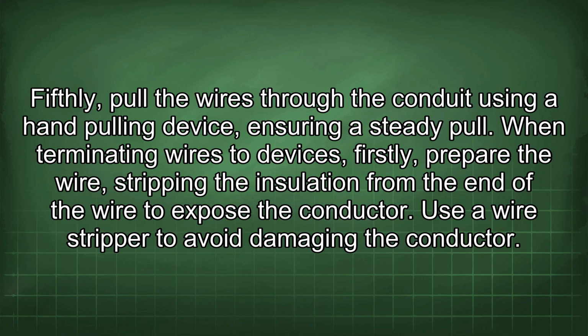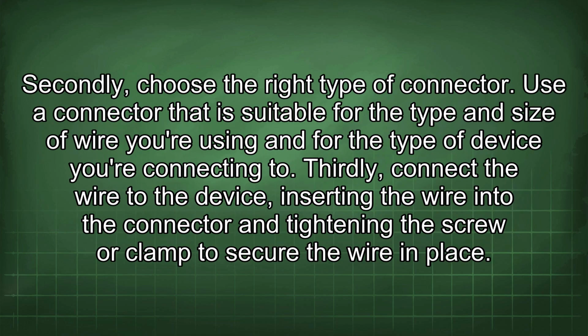When terminating wires to devices, firstly, prepare the wire, stripping the insulation from the end of the wire to expose the conductor. Use a wire stripper to avoid damaging the conductor. Secondly, choose the right type of connector. Use a connector that is suitable for the type and size of wire you're using and for the type of device you're connecting to. Thirdly, connect the wire to the device, inserting the wire into the connector and tightening the screw or clamp to secure the wire in place.